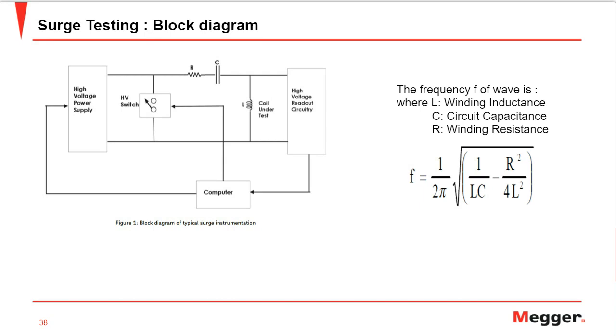The ringing frequency of that waveform is given by this formula. The R squared by 4L squared factor is very low, so we can eliminate it and simplify the equation as 1 by 2 pi times the square root of 1 by LC. If the turn-to-turn insulation fails with an arcing short between two turns of the coil, a fraction of the inductance will be shorted out of the circuit. As the inductance is shorted out, the frequency will increase, because the two are inversely proportional. As the frequency increases, it will jump to the left of that ringing pattern. Of course, we'll see in the next slides what jumping to the left on the frequency or ringing pattern means.